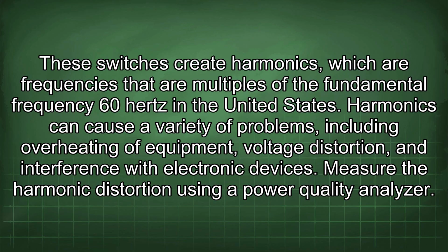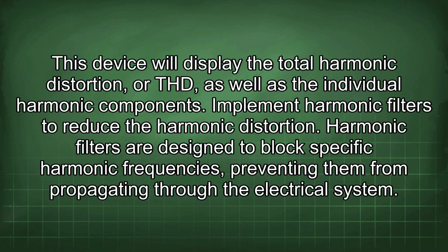Measure the harmonic distortion using a power quality analyzer. This device will display the total harmonic distortion, or THD, as well as the individual harmonic components. Implement harmonic filters to reduce the harmonic distortion. Harmonic filters are designed to block specific harmonic frequencies, preventing them from propagating through the electrical system.